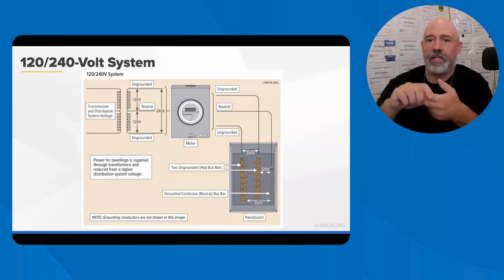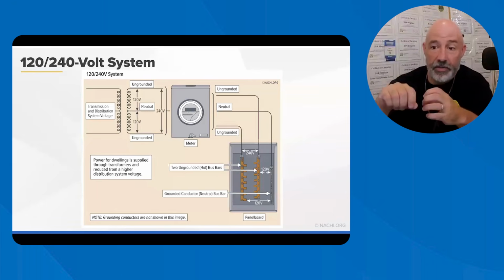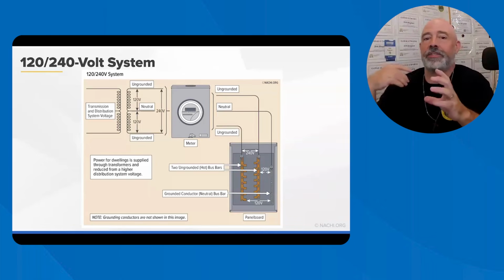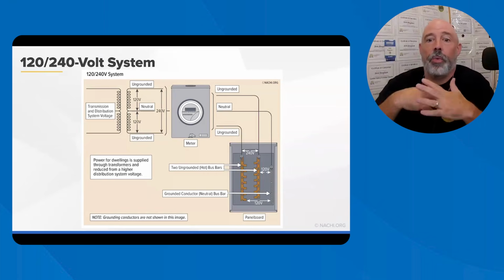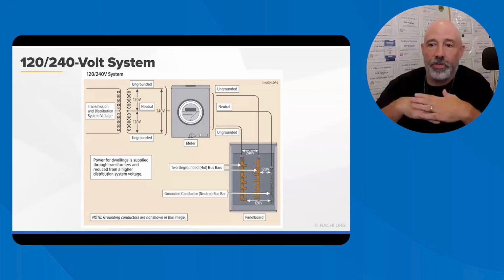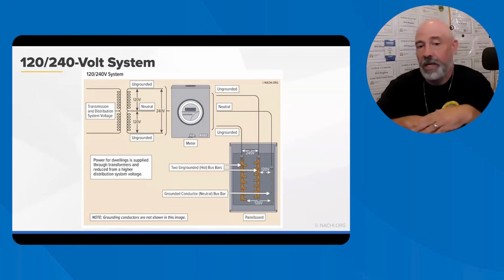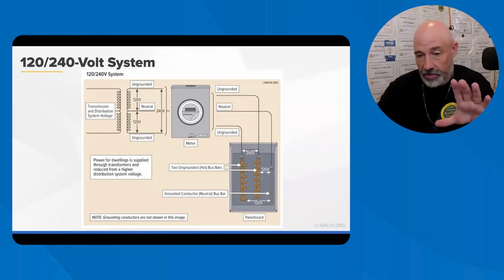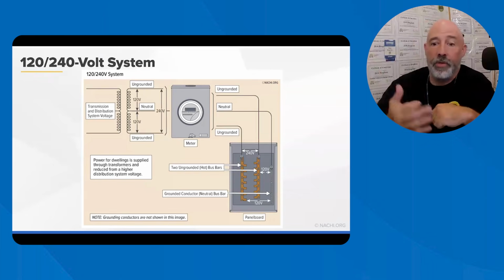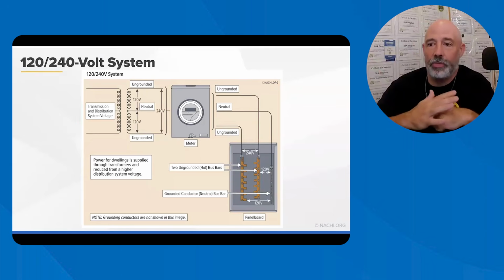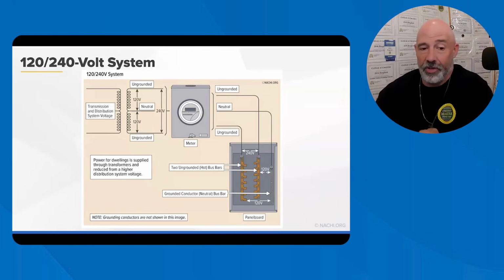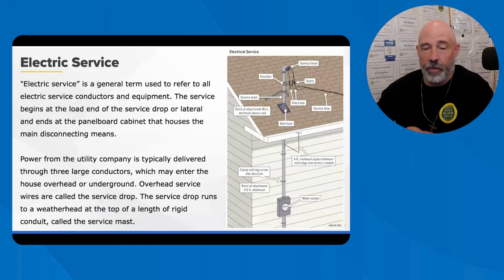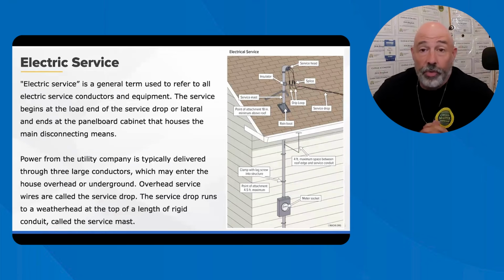The neutral conductor originates from the center tap of the utility transformer and serves as the return path for the 120 volt circuits. While all neutral conductors are grounded conductors, not all grounded conductors are neutral. That's why, when you're doing electrical inspections, the grounds have to be disconnected from the neutrals in the sub panel. Most homes in Europe use a three-phase electrical system, which allows multiple homes to be supplied more efficiently from the same distribution center. Things are a little bit different over in Europe, but the same rules apply when you're talking electrical.